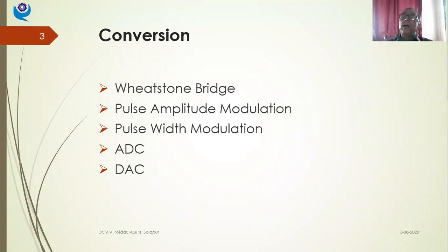If one of the arms of the Wheatstone bridge is sensitive to strain gauges, we call it a single arm bridge or quarter bridge. If two arm resistances are removed and replaced by two strain gauges, we call such a circuit a two arm sensitive bridge or half bridge.